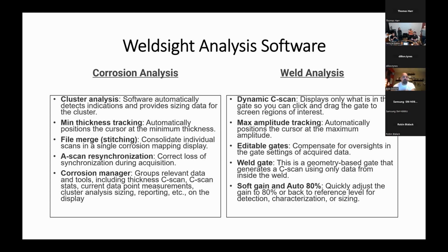Weldsight for corrosion analysis. Some features that it has in there: we've got cluster analysis. The software automatically detects indications and provides sizing data for the clusters. When you have lots of small indications grouped together, all in one spot, it will cluster those together and give you the data on individual points, or give you the min and max. That's amazing. It'll automatically position the cursor at the minimum thickness when you're scanning or doing your corrosion analysis.